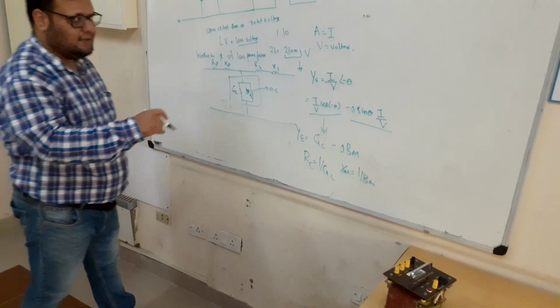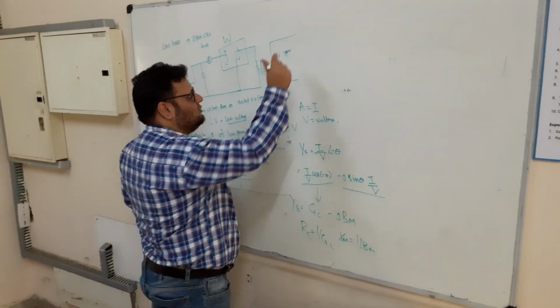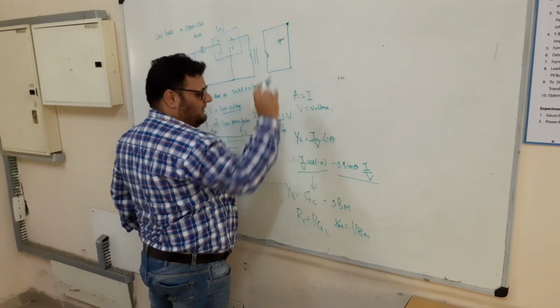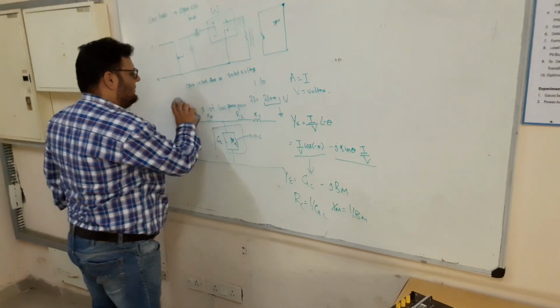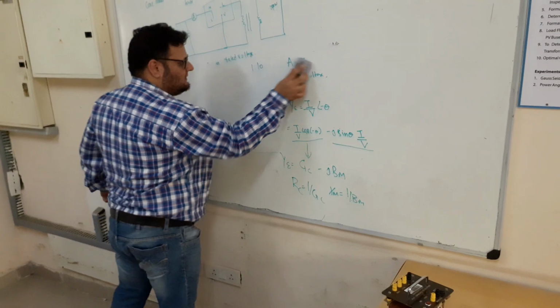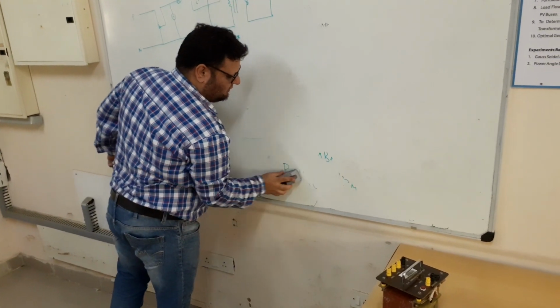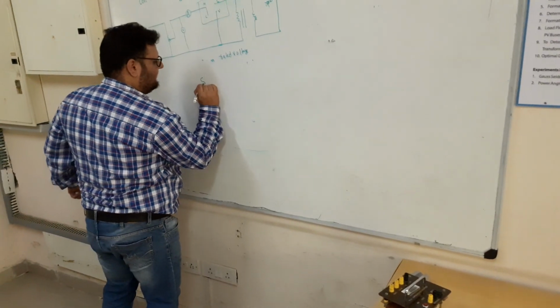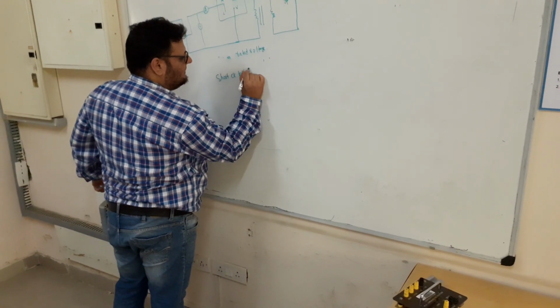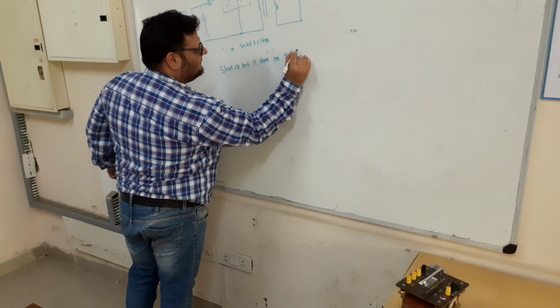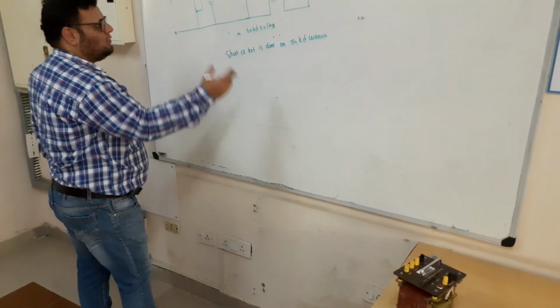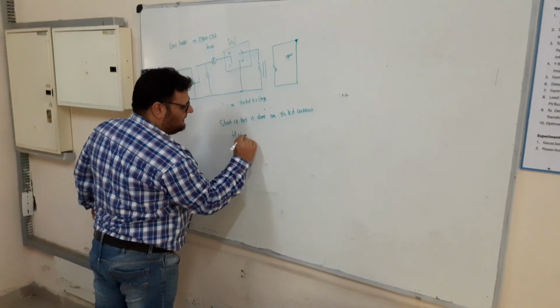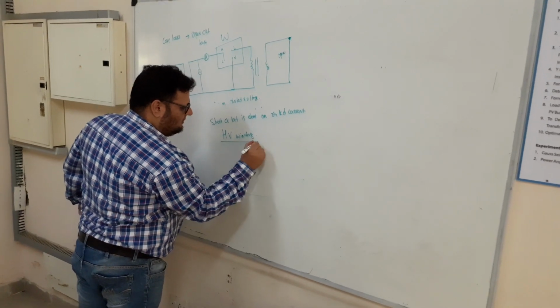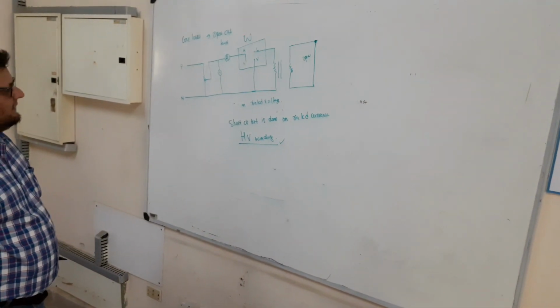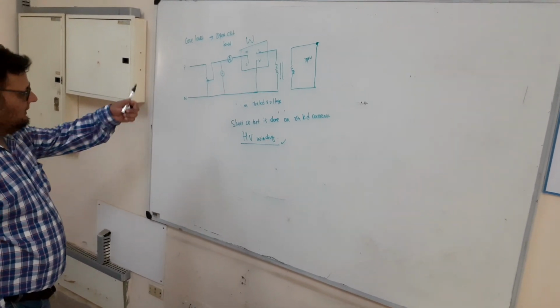In the short circuit test, what you will do is short the secondary side, the windings. The circuit diagram will remain the same. The short circuit test is done on rated current, and the open circuit test was done on rated voltage. Whereas the open circuit test used the LV winding, the short circuit test is done on the HV winding, for obvious reasons: the current rating is reduced on the HV winding. And from the short circuit test you will get your copper loss.